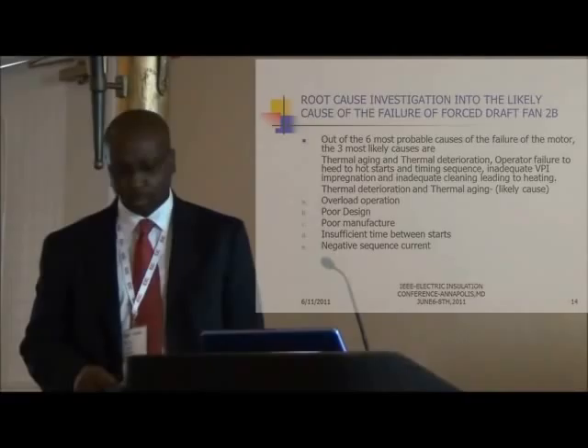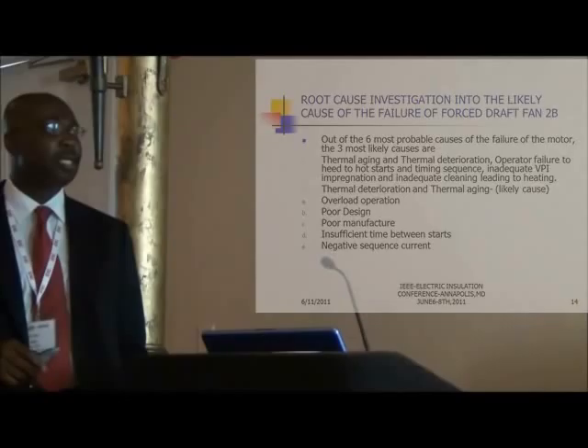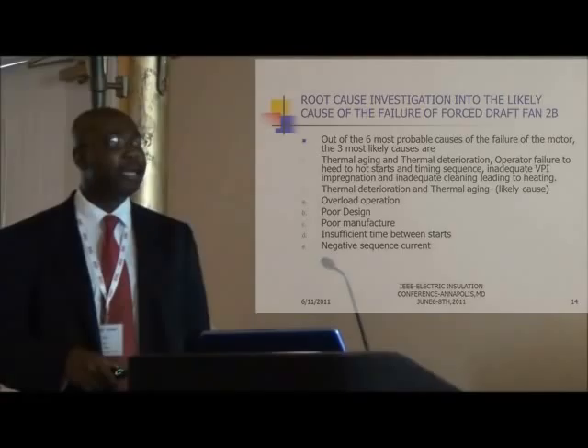When we conducted the root cause investigation, we initially found six most probable causes. Out of those six, we determined the three most likely causes to be: thermal aging and thermal deterioration, operator failure to adhere to the hot and cold starting sequence, and inadequate VPI impregnation along with inadequate PMs at the station.